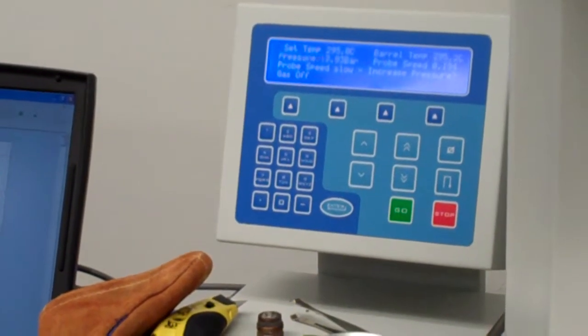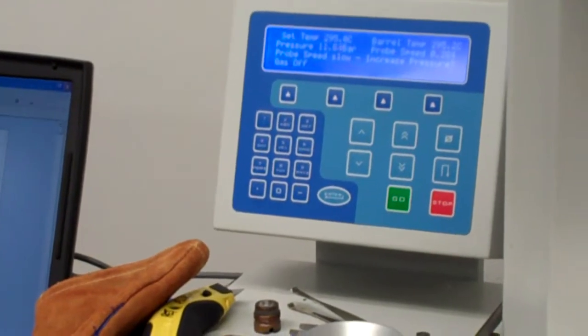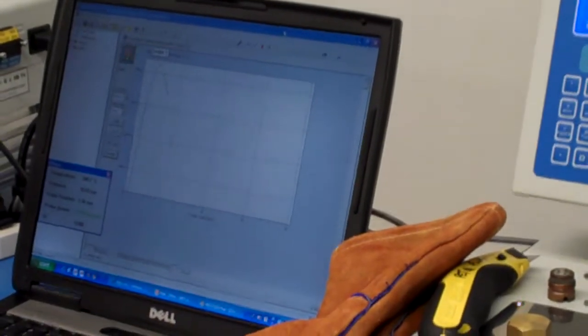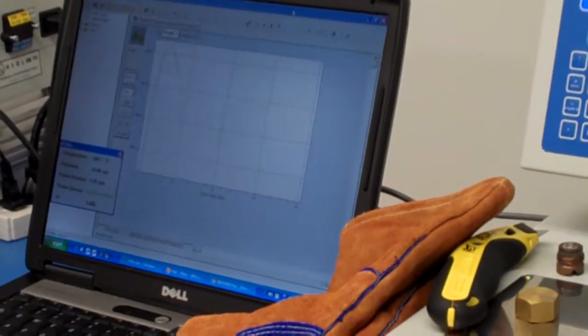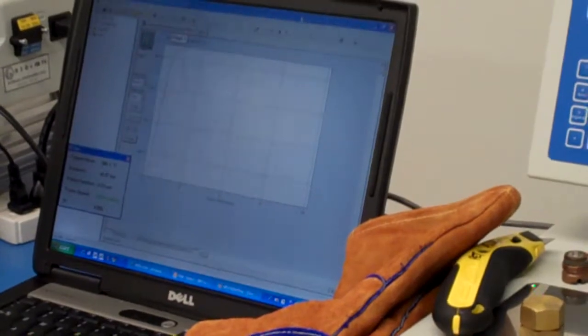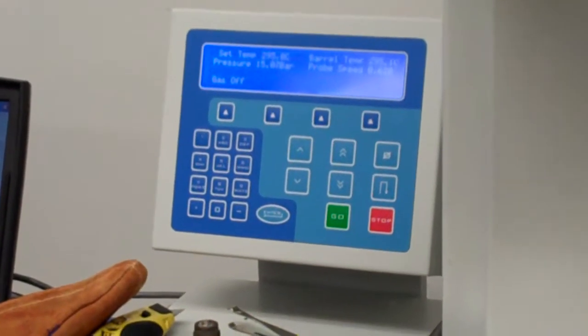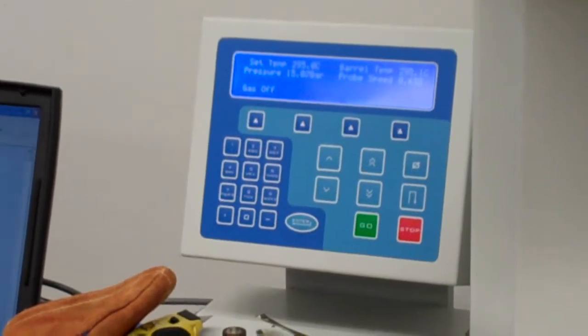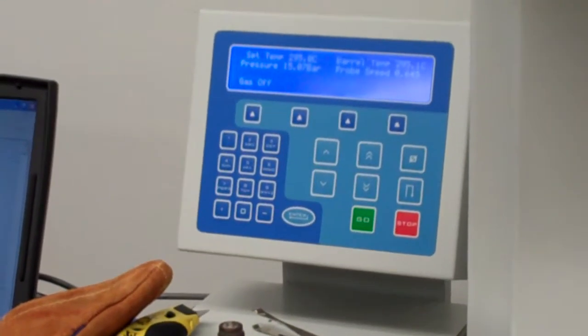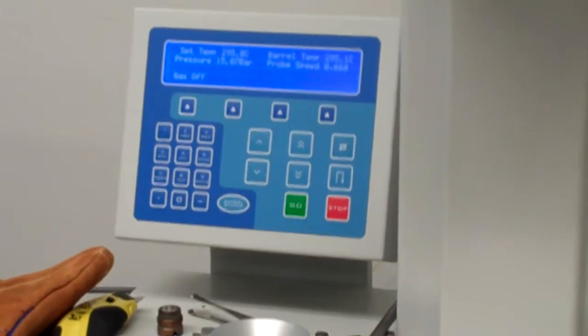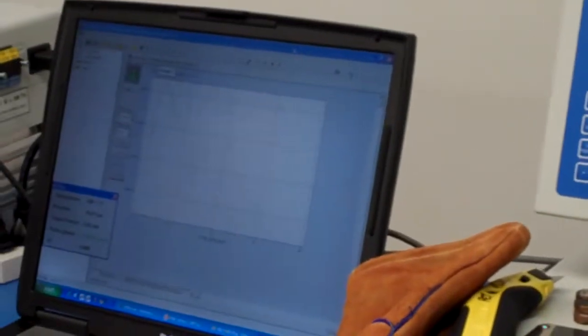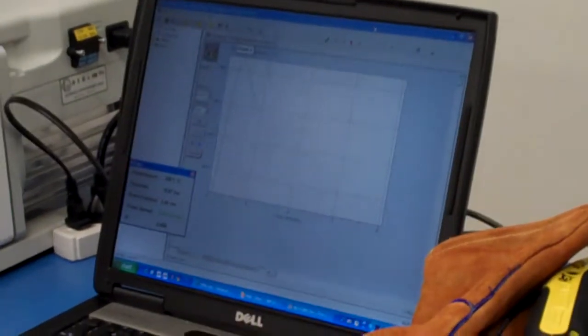How do you know you only have a minute? I'm going to turn it way up because I know that it needs... You have five minutes before your test starts. I know that it needs quite a lot more pressure. Do you have to do that for each test? Do you have to adjust the nitrogen? Only if it's a new material because the next time we do it, we know which pressure to use. So it's already pre-set? It's not pre-set. We might finish at 15 or 20 bar, in which case we'll just leave the thing where it is for the next test.